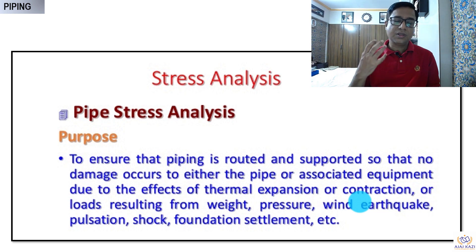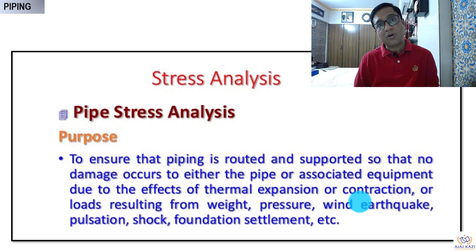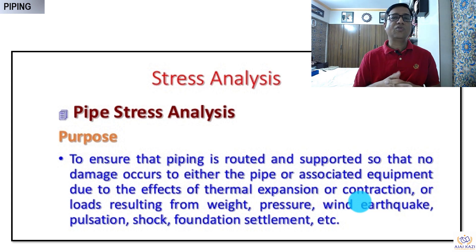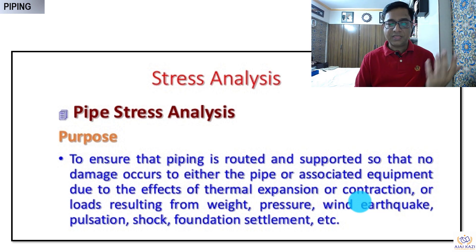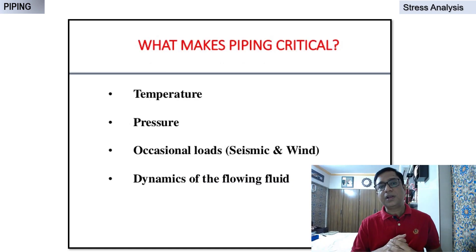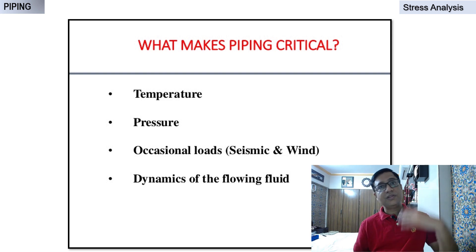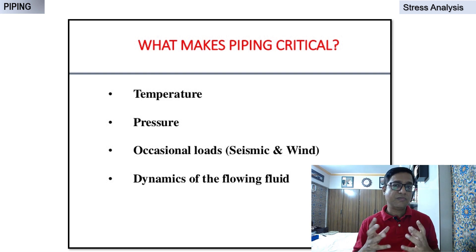The purpose of proper support is so that no damage occurs either to the pipe or associated equipment, because pipes are connected to various equipment. Damage can result from thermal expansion, contraction, load from weight, pressure, earthquake, or anything else. These combinations are used in stress analysis software to determine what makes piping critical. Key factors are the temperature of the water or fluid, the pressure, occasional loads such as seismic or wind load — especially important on top of buildings — and the dynamics of the flowing fluid.